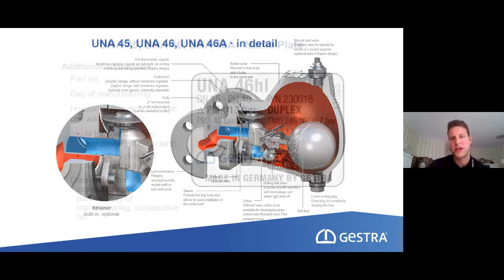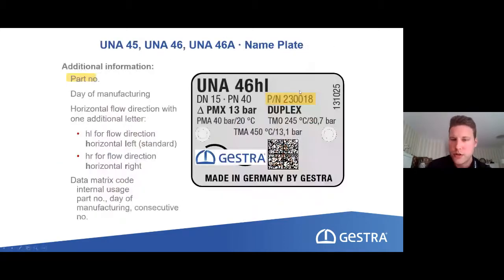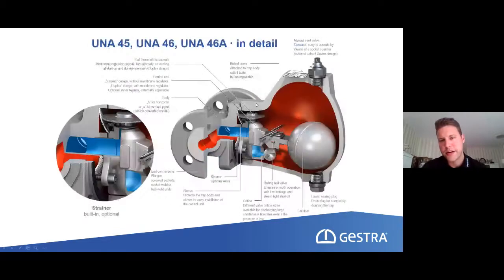And what was, let's say, the original installation, you can see here on the nameplate. So this was a horizontal installation, and the second letter we see here is an L, and this L stands for left, and it tells us, okay, it's horizontal left, so the flow direction is from left to right. We could also have the opposite way, so there would be an R, we could go from right to left, and this will change where we find the body of the steam trap.